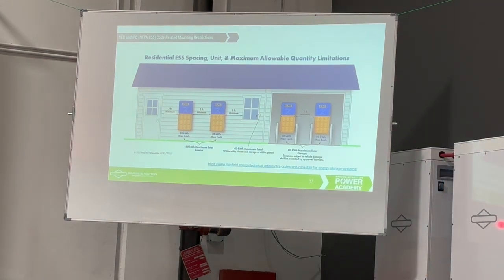But now it's 100% true that for a jurisdiction like LA County, no matter what the manufacturer spec or UL certification says, they still want to go with 36 inches. Like you mentioned, it depends on the jurisdiction, but if you guys start from the beginning with 36, that's the way to go. We have very few cases where we communicate with the AHJ and they change their mind, so normally if that's what they want, that's what you have to go with.